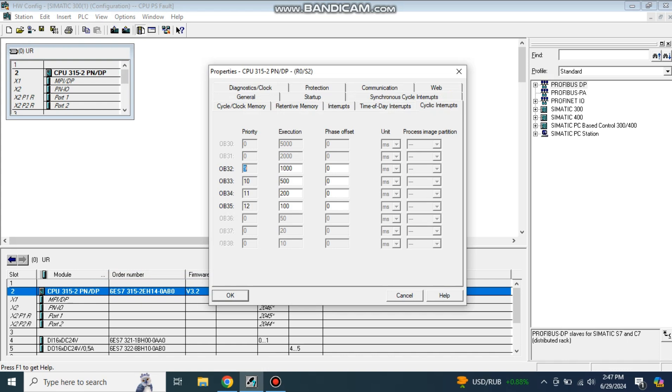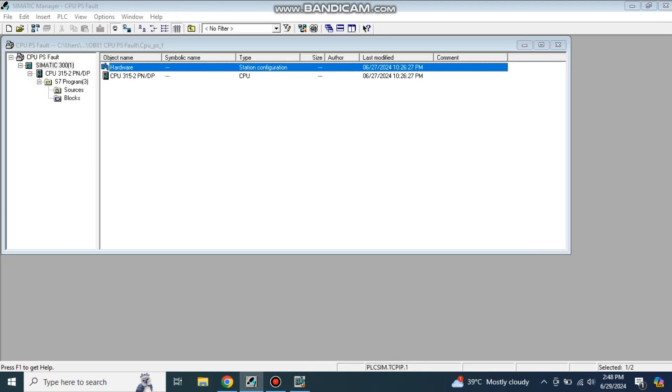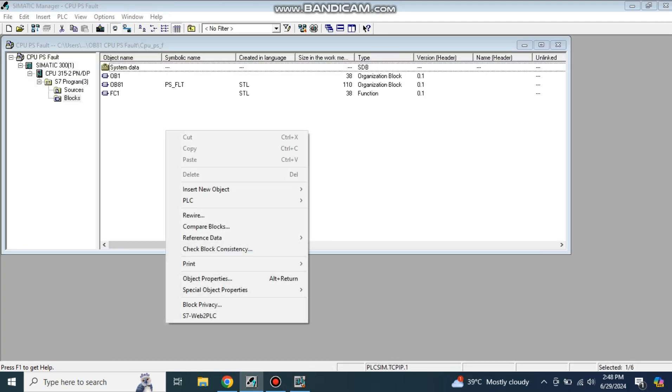These are the execution times that show after how many milliseconds it will execute automatically. This is 1000 milliseconds which is actually equal to one second. You can change it. As it is default 1000, I'm not going to change it. I will take the cyclic interrupt OB32 in my program. Keep in mind this execution time is 1000 milliseconds which is equal to one second. Click OK.